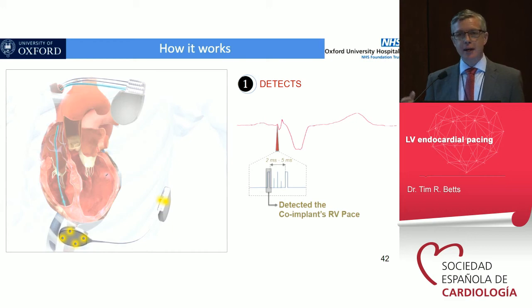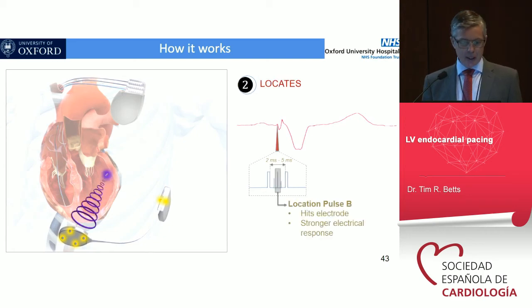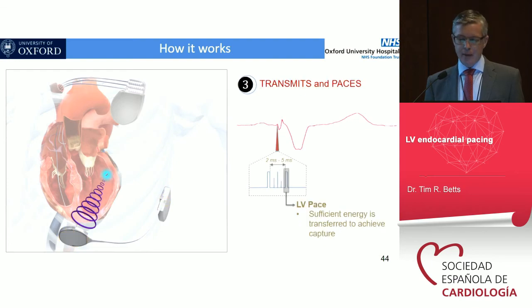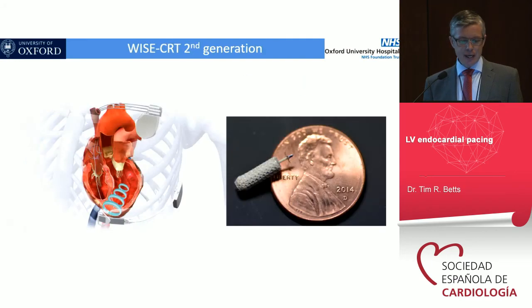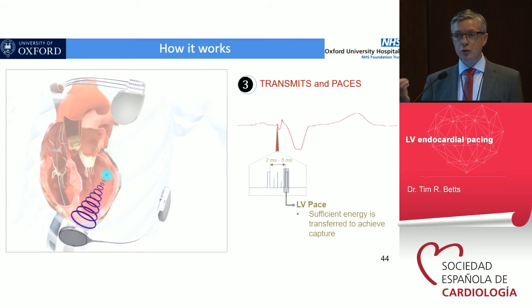When the indwelling right ventricular lead stimulates the right ventricle, when they are paced, the system picks up the pacing spike. It then immediately sends out a pulse of ultrasound directed towards the left ventricular receiver, and that piezoelectric crystal is able to convert that acoustic energy into electrical energy and stimulate the left ventricle. It does this within about 4 milliseconds of the pacing spike, so you get simultaneous left ventricular stimulation.